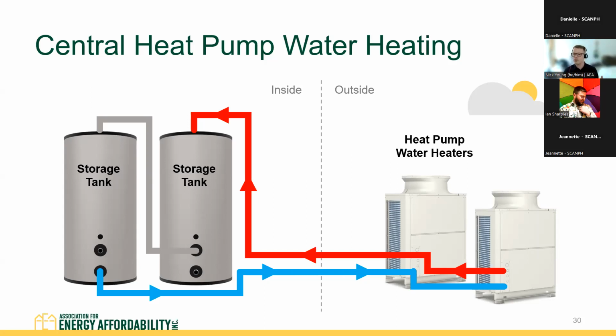So with electric systems, it's beneficial to design your system to run at a lower capacity for a longer period of time, as opposed to a higher capacity for a very short period of time. Tankless systems turn all the way on for a minute and then all the way off, which is a recipe for very high demand charges. Instead, with heat pump water heaters, we design very large storage tanks, a big thermal battery. Then we have very efficient heat pumps that simmer for many hours and slowly recharge that storage system, either overnight when electricity is less expensive, or during the day when there's a lot of solar on the grid or from the building. So the heat pumps recharge the storage tank, and the storage is there to meet your demand.